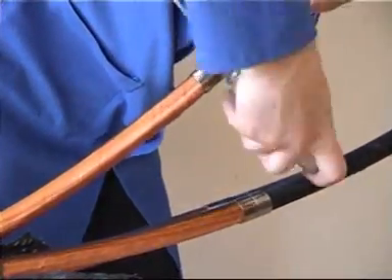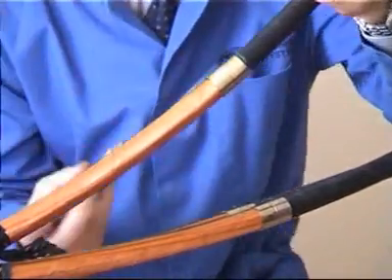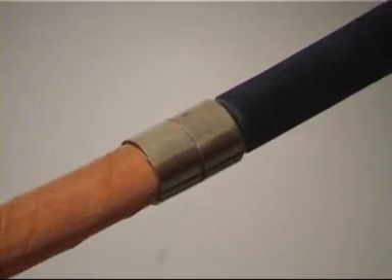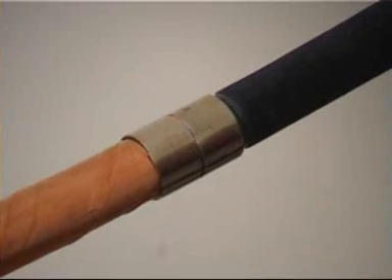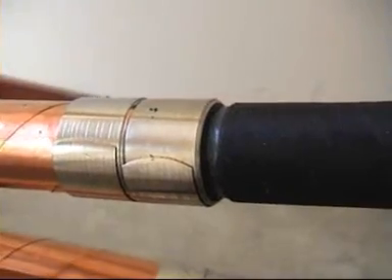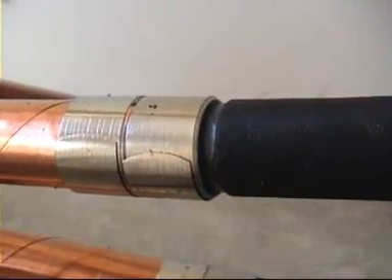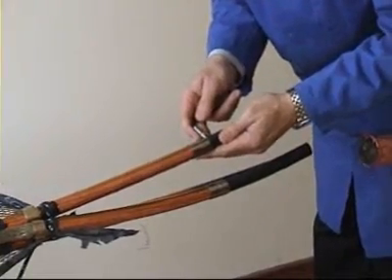Using a file to create the screen cut may seem like a crude method. However, it does produce a very good tapered edge. And don't worry if you go slightly into the primary insulation. The yellow stress tape will fill this at a later stage.